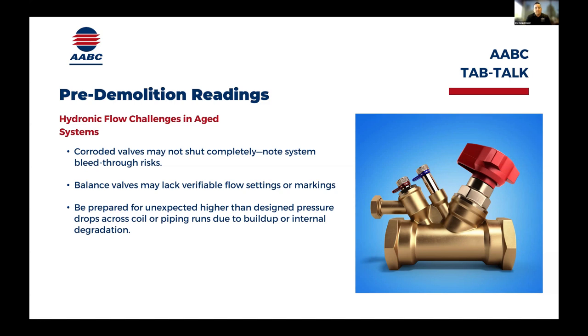We talk about this quite often - having multiple sets of data when you're doing test and air balance definitely can help, because then you're taking two different sets, and if they equal each other, you can feel pretty confident that's the flow you're getting. When they don't equal, you have to do some troubleshooting to figure out what's happening, why you have a reading that doesn't equal what you think the flow should be.